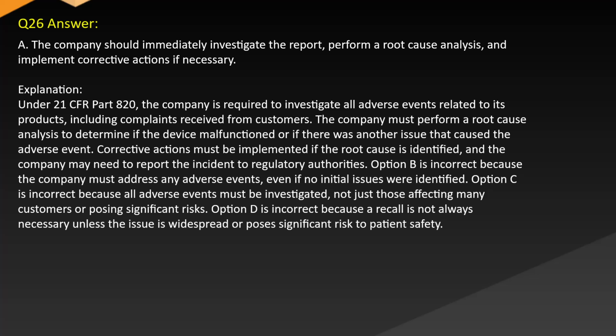Answer A. The company should immediately investigate the report, perform a root cause analysis, and implement corrective actions if necessary. Explanation: under 21 CFR Part 820, the company is required to investigate all adverse events related to its products, including complaints received from customers. The company must perform a root cause analysis to determine if the device malfunctioned or if there was another issue that caused the adverse event.